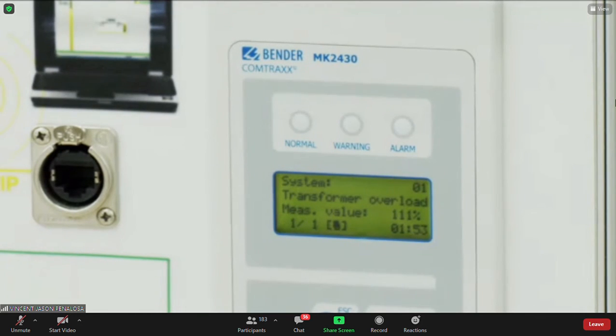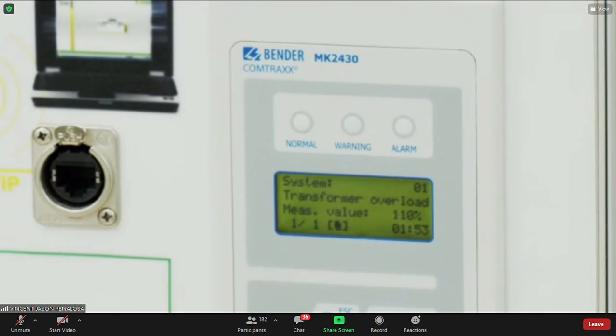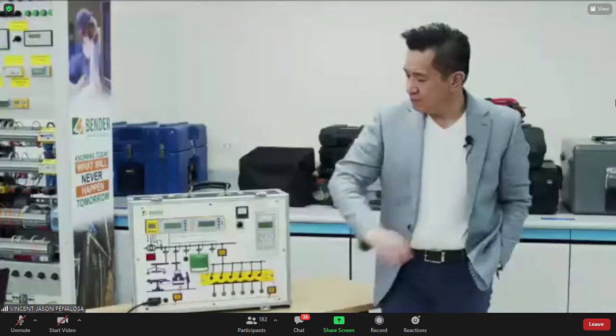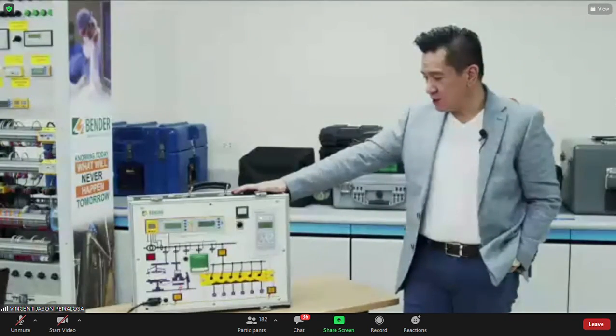They say that I put in a load of about 110%. So I'm overloading the transformer, and we don't like that. Chances are, if that is actually correct, that I'm loading it by 110%, right? If I'm loading it by 110%, even the temperature sensor will go off. The temperature alarm will go off. All right. So let's see if that shuts down on me. Yes, it shuts down on me.